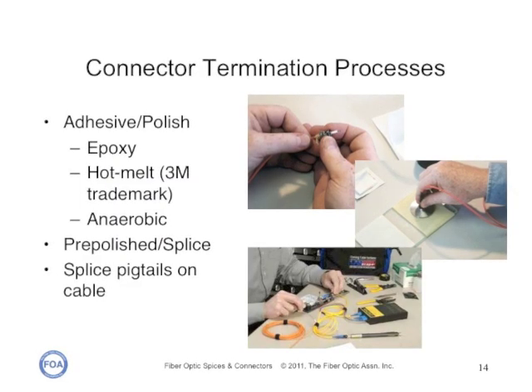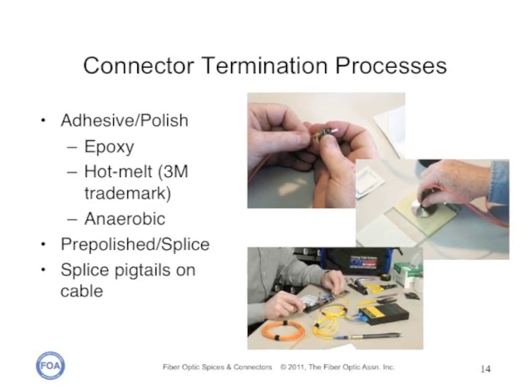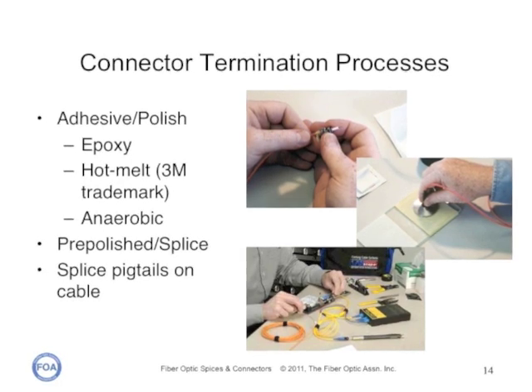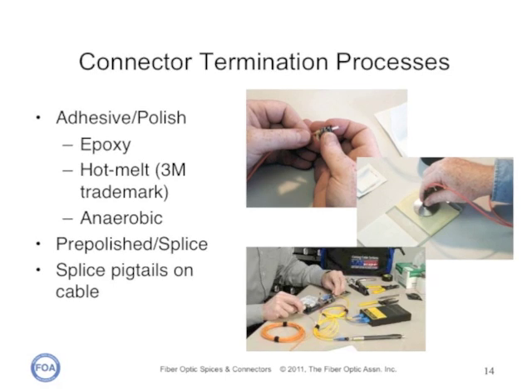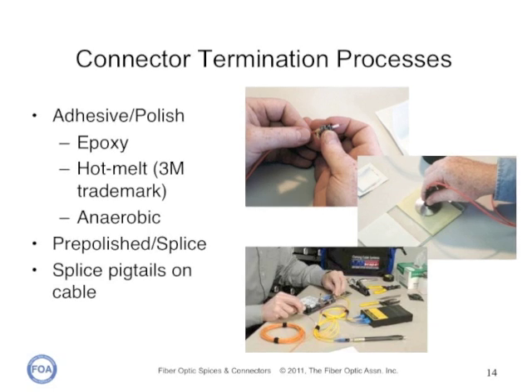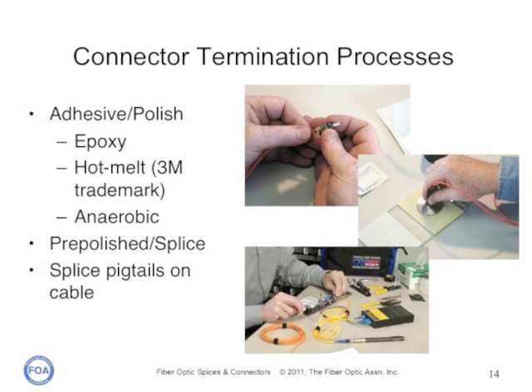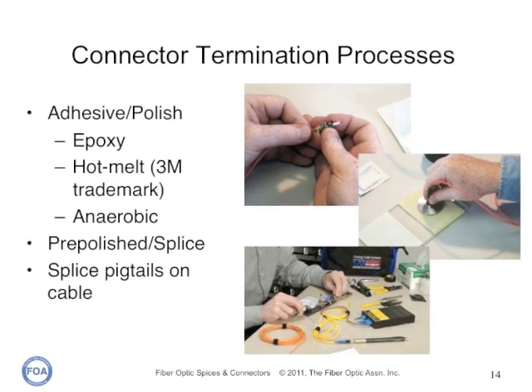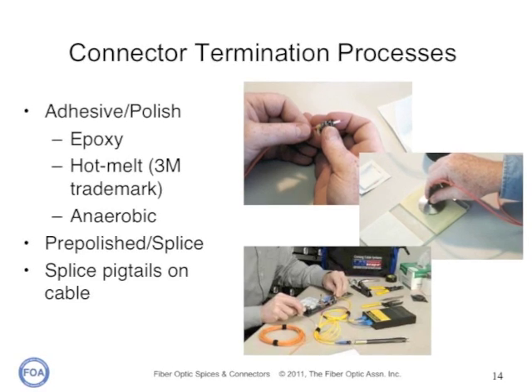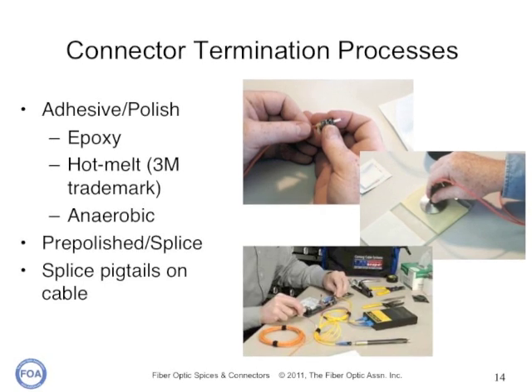A lot of the development of fiber optic connectors has gone into finding new ways to terminate fibers easier, simpler, and cheaper. Most connectors use an adhesive and polish technique with some type of adhesive and a polish at the end of the ferrule to get a good optical interface. You can also get pre-polished splice connectors, which are already polished and have a splice in the back shell of the connector. In single mode fiber, the preferred method is usually to splice on a terminated pigtail with a fusion splicer to get the lowest loss and least reflectance.